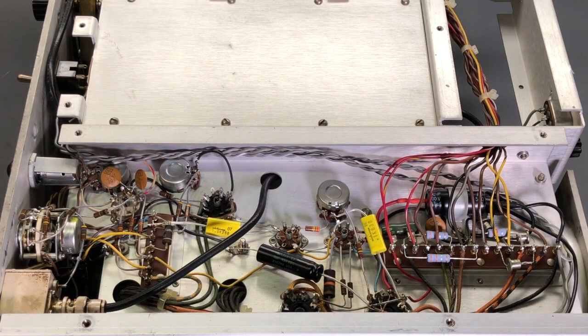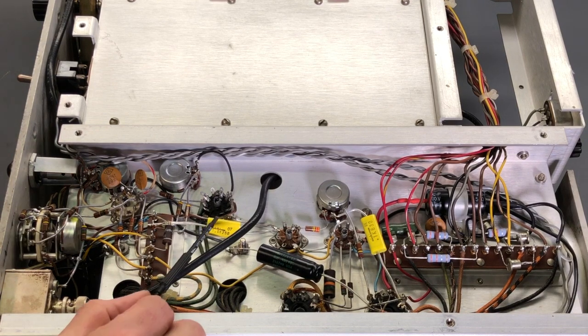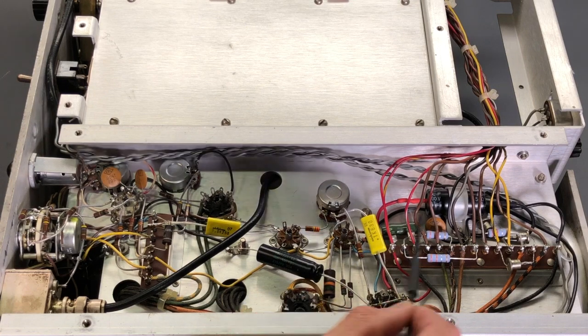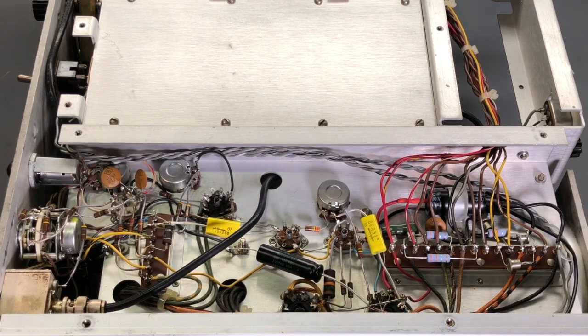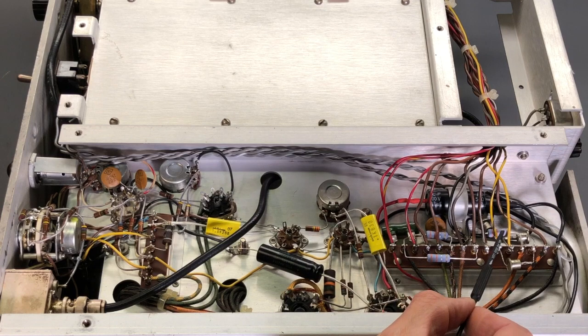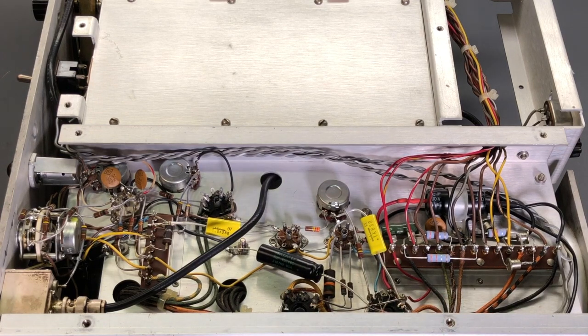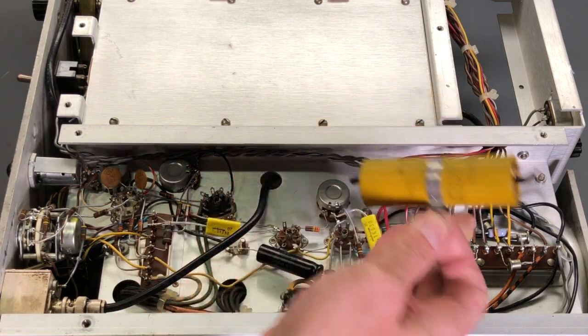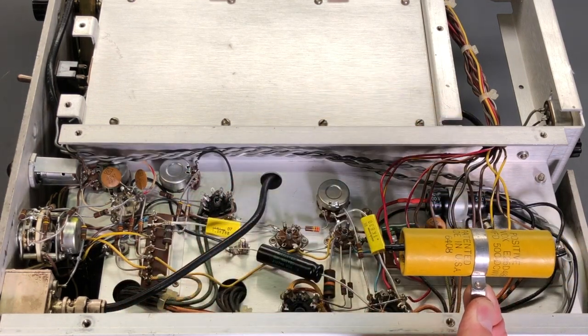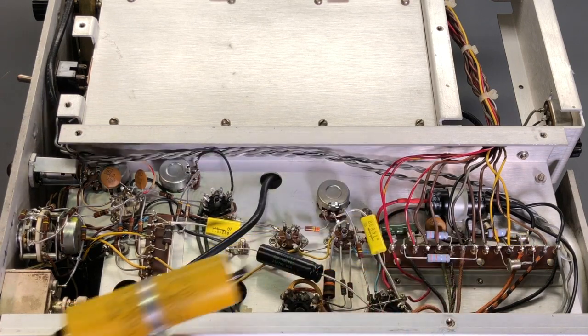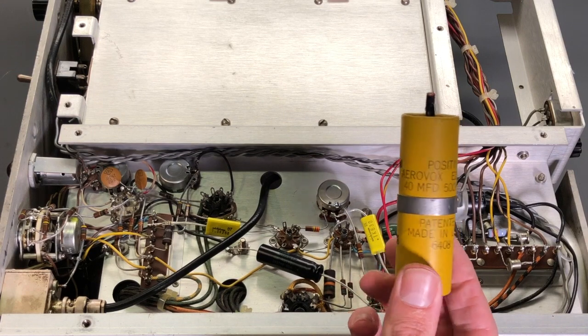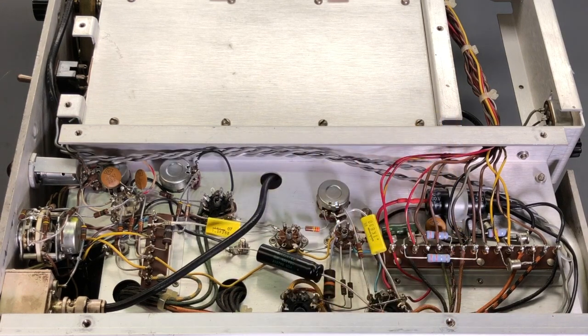Okay, here we are looking at the bottom of the chassis again, and you can see the various components that I've replaced. So we have the 4 capacitors here, here, here, and this one in the clamp right here. And then the 3 resistors here, here, and right here. So you can see there's a noticeable difference in size on the capacitors on the old versus the new. So this capacitor right here and the old capacitor, you can see there's a considerable difference in size. Now this old capacitor was rated 40 microfarad at 500 volts, and the new capacitor is 47 microfarad at 500 volts.